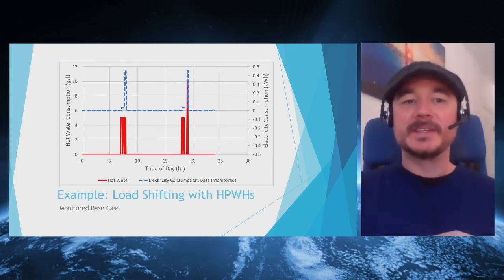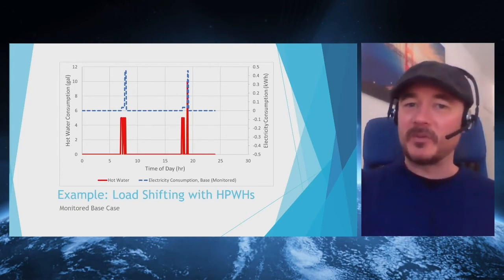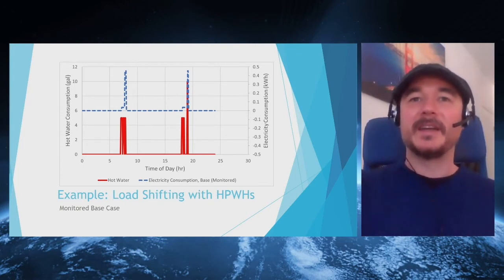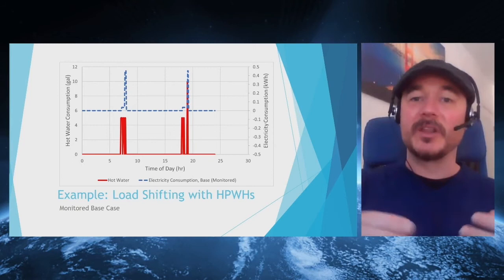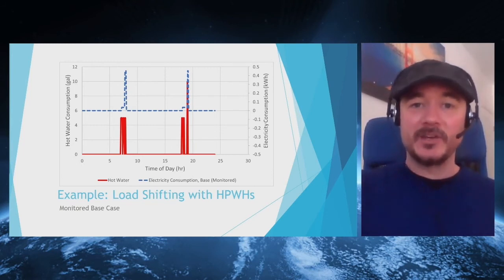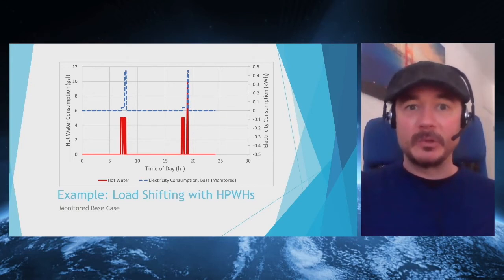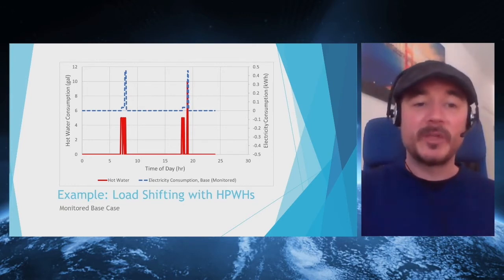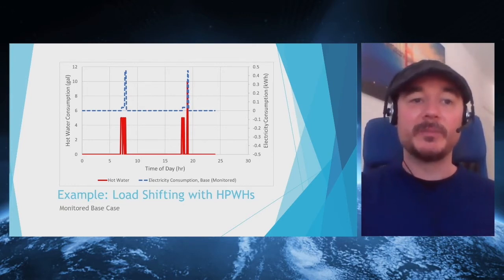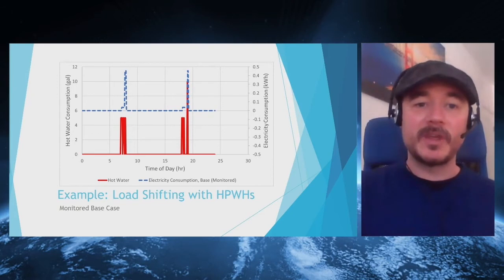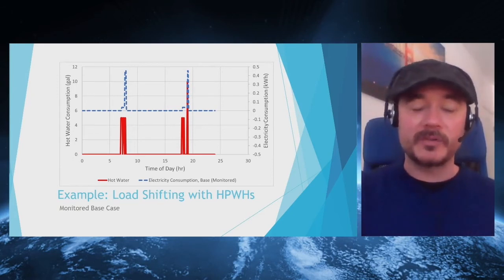But then there's not enough storage. The heat pump doesn't have enough capacity. Halfway through the third shower, the electric resistance element has to engage to make sure the occupants can get hot water. It's possible, not likely but possible, that the third shower got cut short for cold water reasons. So it keeps using the electric resistance element to get the water in the tank back up to the set temperature so it's ready for the next person.